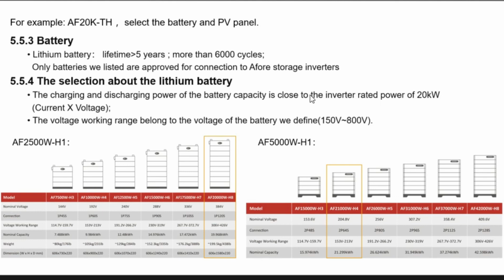And for the battery side, a three-phase inverter only works with a high voltage battery bank. The stackable battery right now comes in the normal version. For the normal version, the minimum battery pack count should be 3 because the lower threshold of battery voltage is 150, so you need 3 packs together to reach this threshold. But for the plus version, the lower threshold of battery voltage starts from 80, so in that case you can connect only 2. That works. So based on the energy usage of the user, you can choose a stackable design from 3 up to 8.